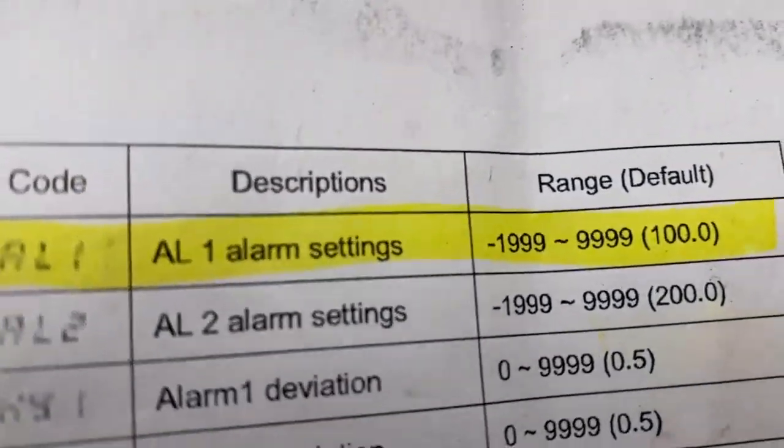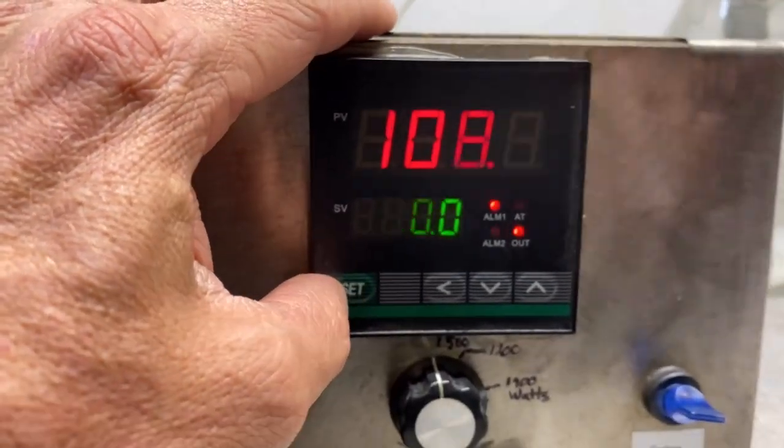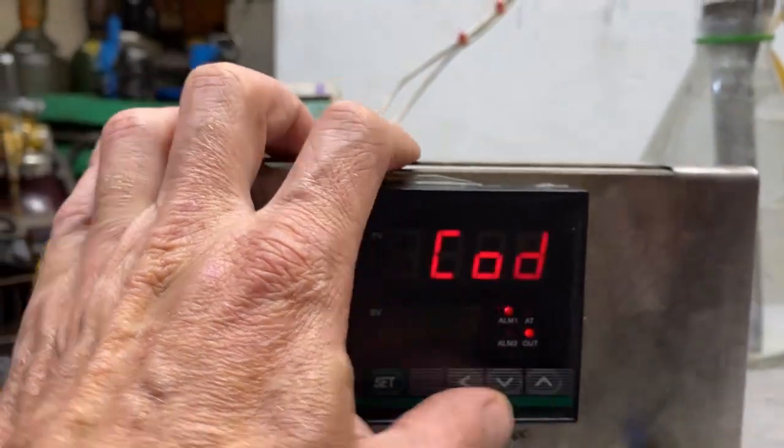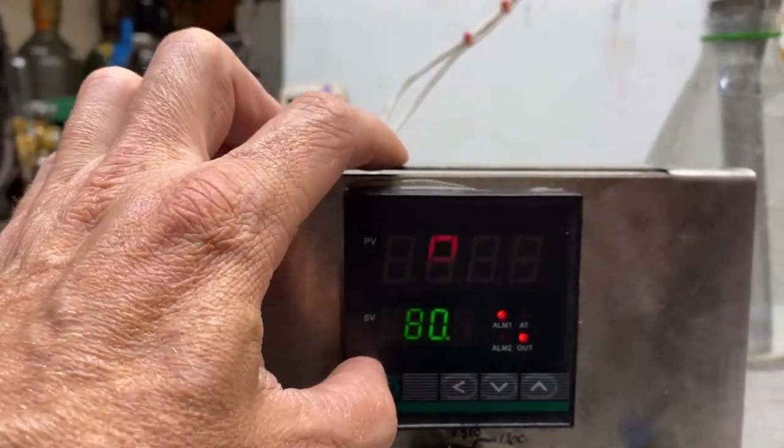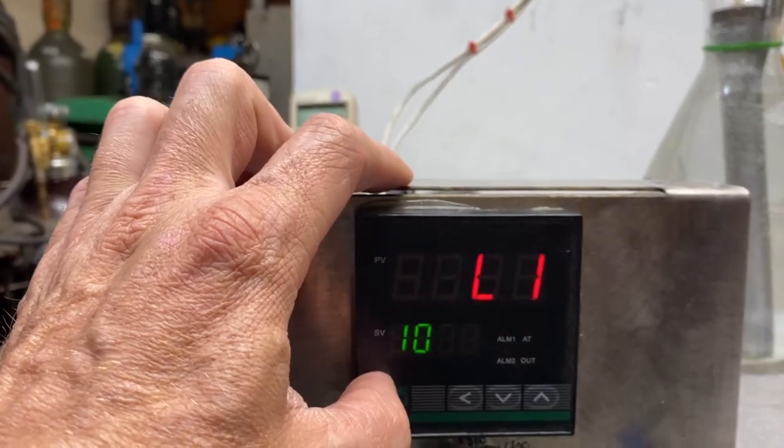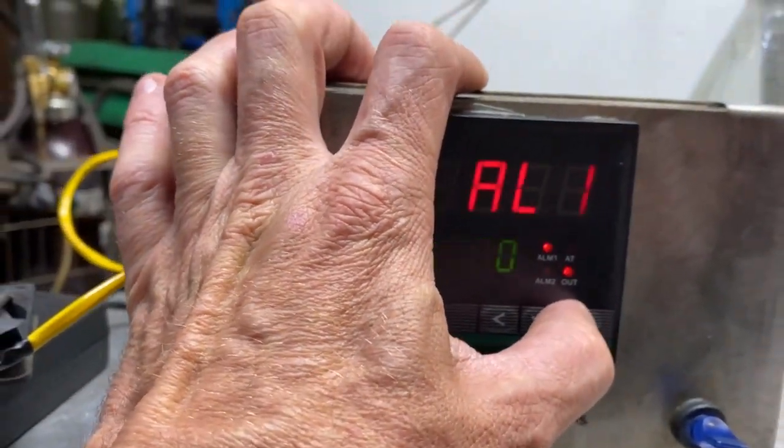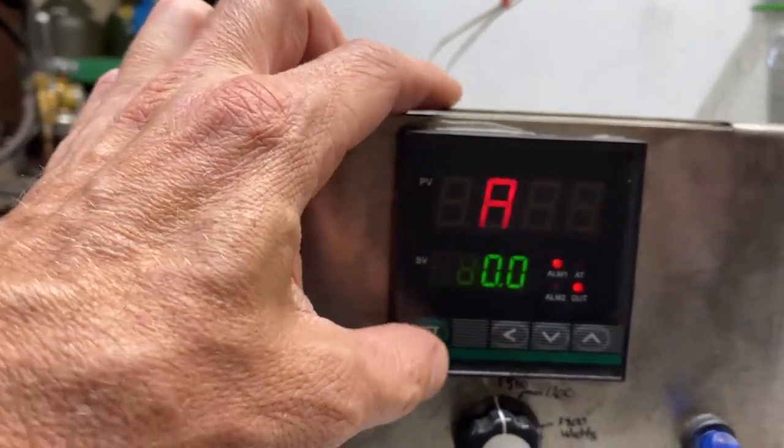So how do we do that? We go to alarm one. To get to alarm one, we go to COD one. And then we're going to come down. Oops, I just passed right through it. I did it again. Alarm one, you see, we have it set here to 105. I scrolled over. We're going to go to 110 to have them both set.